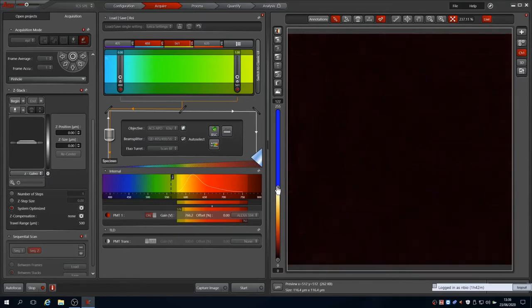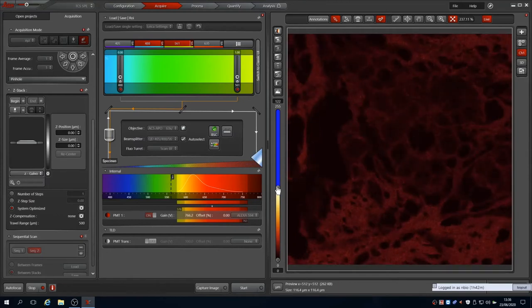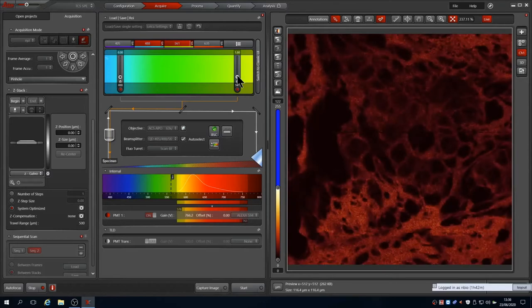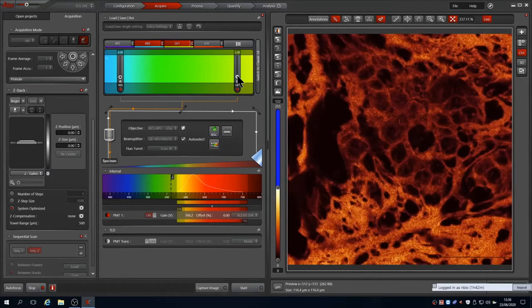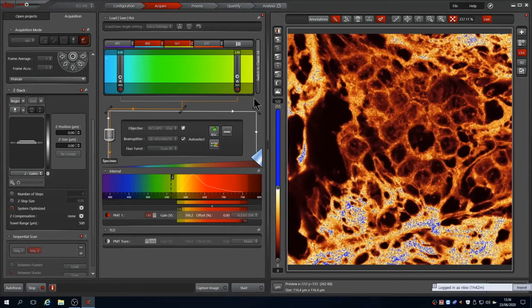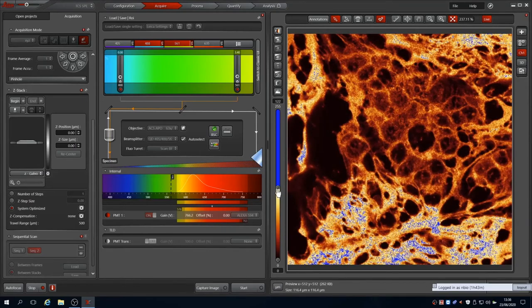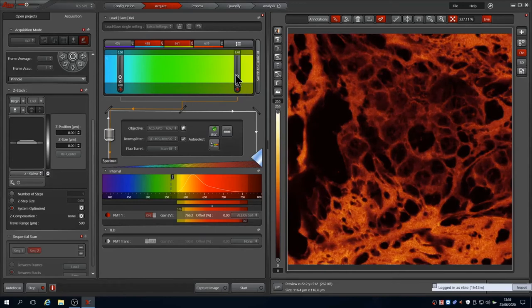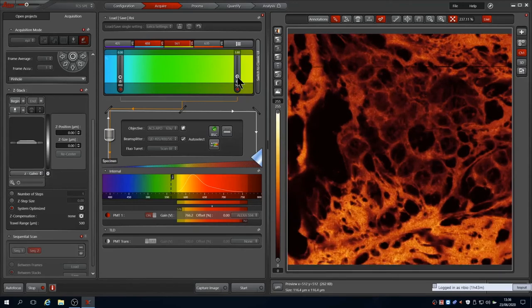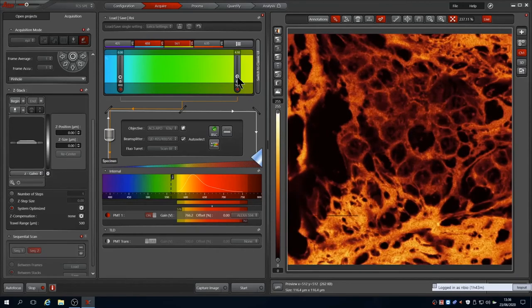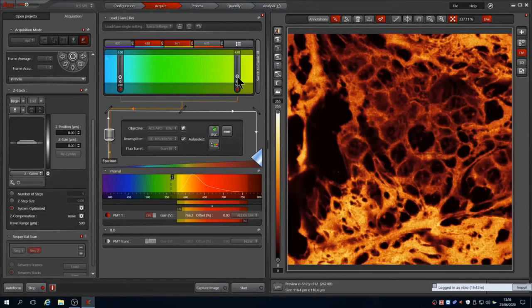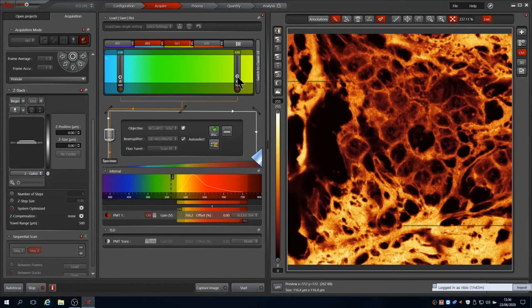At this point, I am double checking the focal plane is correct by adjusting the fine focus backwards and forwards to ensure I am in the correct or brightest plane. Once happy with this, we can improve the signal. Since we have a reasonably high PMT gain, we can do this by increasing the excitation power. Doing this shows some pixels as blue with the range indicator LUT, suggesting they are saturated. This is only because we have clipped the LUT range.